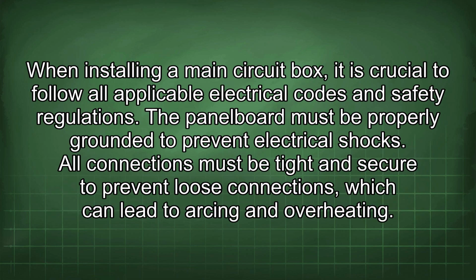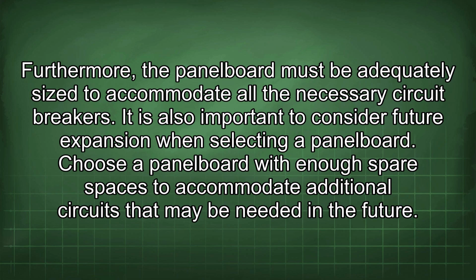When installing a main circuit box, it is crucial to follow all applicable electrical codes and safety regulations. The panel board must be properly grounded to prevent electrical shocks. All connections must be tight and secure to prevent loose connections, which can lead to arcing and overheating. Furthermore, the panel board must be adequately sized to accommodate all the necessary circuit breakers. It is also important to consider future expansion when selecting a panel board. Choose a panel board with enough spare spaces to accommodate additional circuits that may be needed in the future.